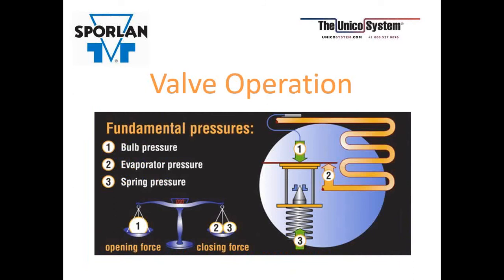Let's begin by talking about how the expansion valve works. We'll start with the 3 fundamental pressures that control the valve. One is the bulb pressure. The constituents in the bulb are designed to provide the opening force of the TEV by mimicking the pressure-temperature relationship of the refrigerant being used in the system. In most cases for Unico, this is going to be either R410A or R22.